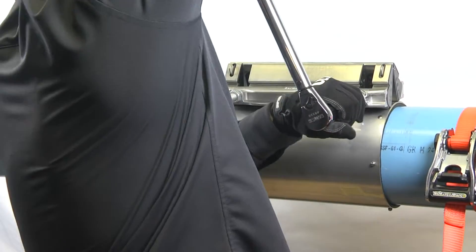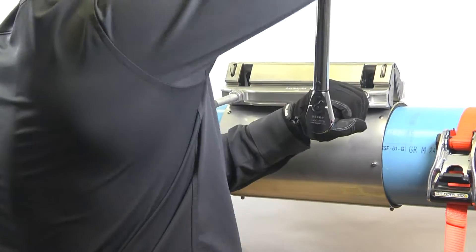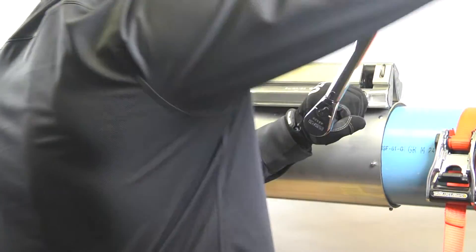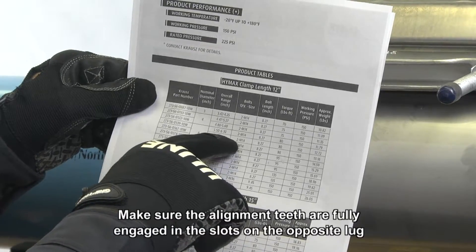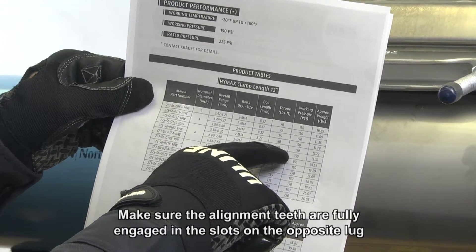Tighten the nuts from the center of the lug outward. Tighten all nuts to the recommended torque as directed on the product label as evenly as possible.